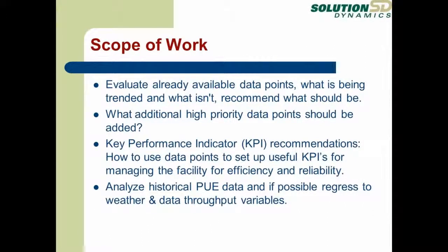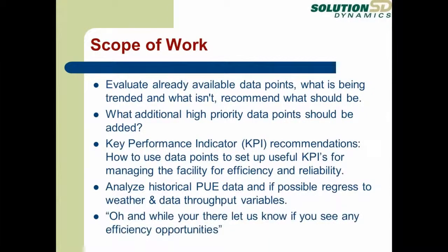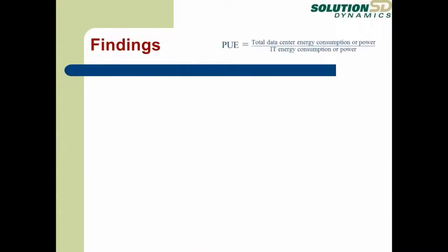They also wanted us to look at their PUE, how they were measuring it, and make suggestions. Was there a way to take out these weather effects to do a regression analysis so that we could see how the PUE was doing without weather factors? And while you're there, let us know if you see any other efficiency opportunities. So that was kind of an add-on that was added at the end.